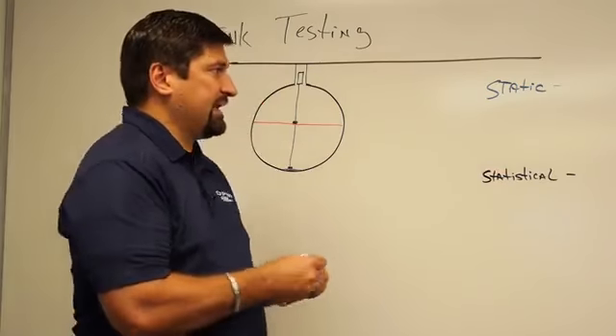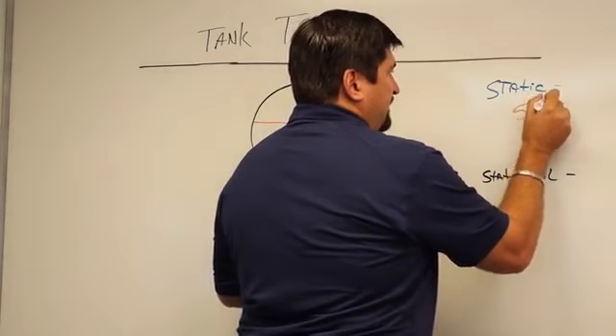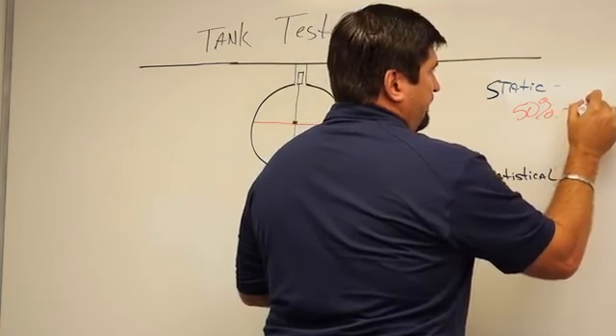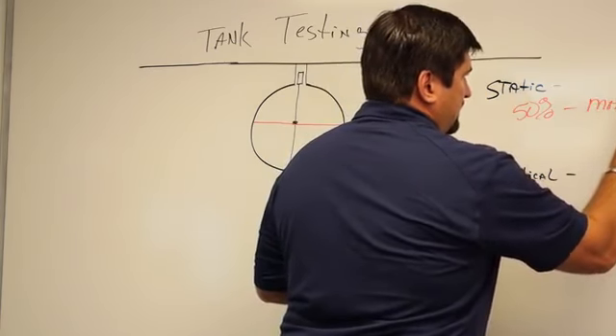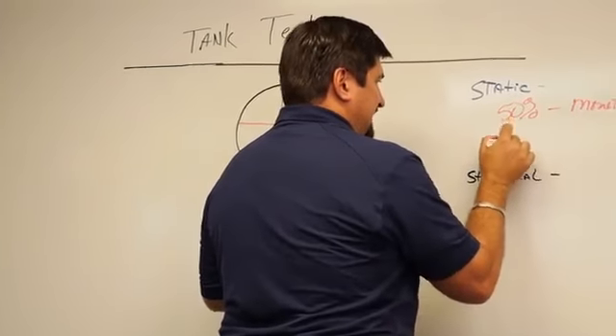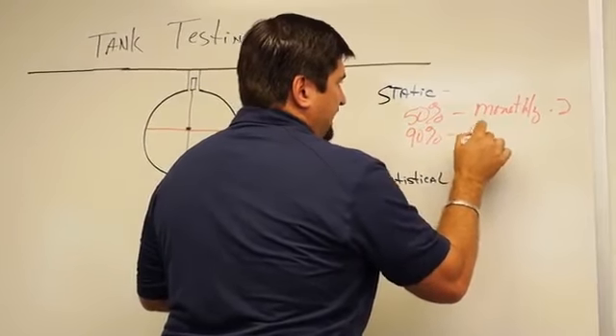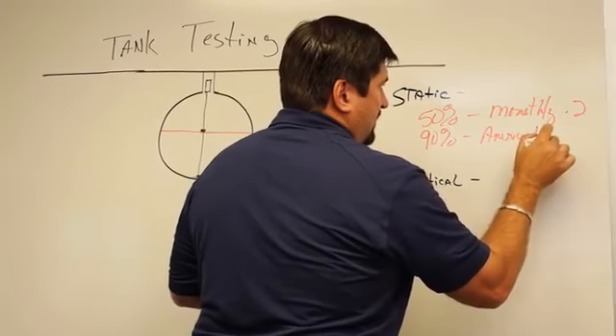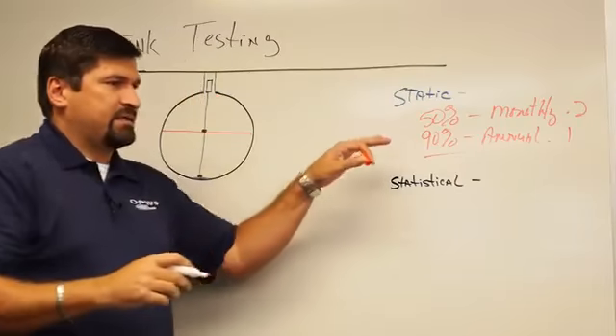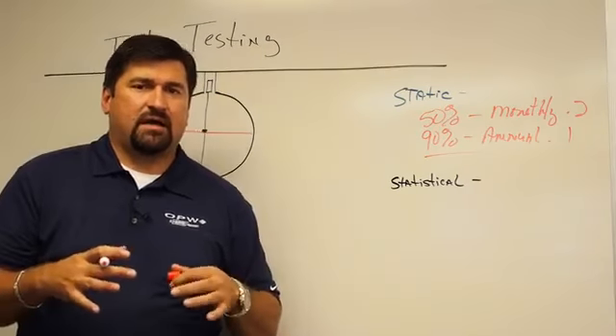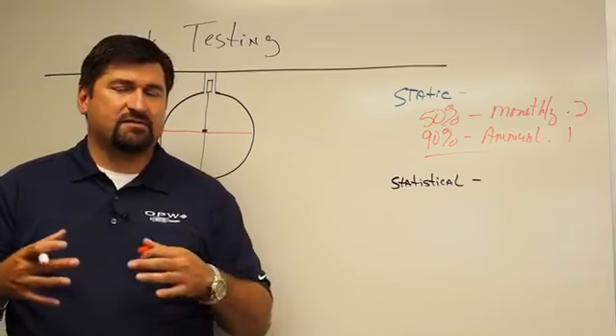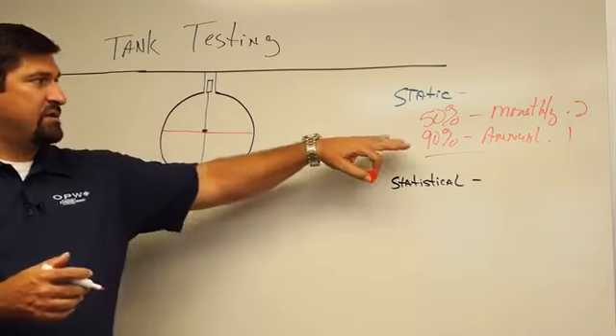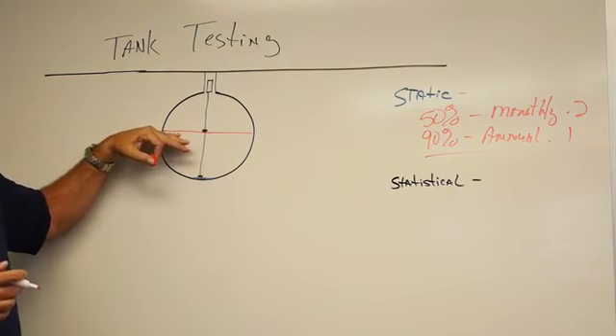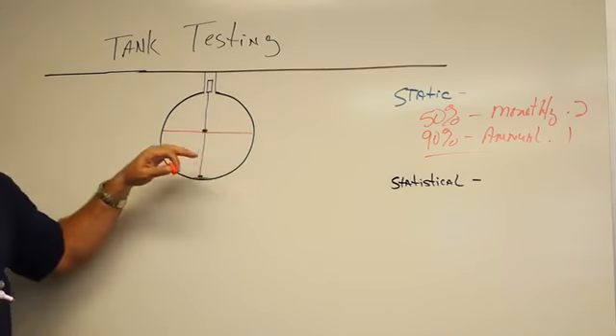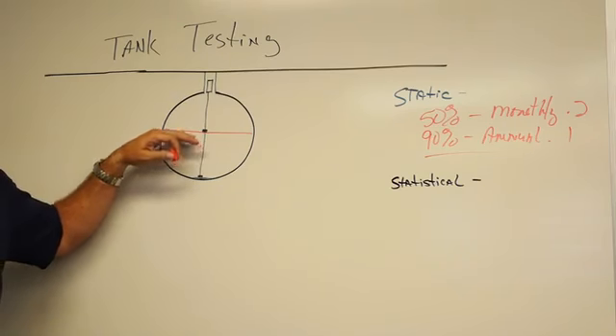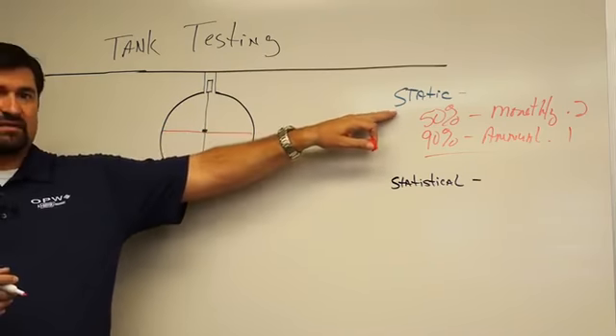So when I look at a static test, I have to be 50% full for a monthly 0.2, and I've got to be 90% full for an annual 0.1. Now, this is why people will buy statistical tests, because they don't want to have to take that tank out of service for long periods of time. So think about this when I'm running a static test. If I have to be 50% full for a 0.2, most of the time it takes at least 6 to 8 hours after a delivery before I can even attempt to run a static test.